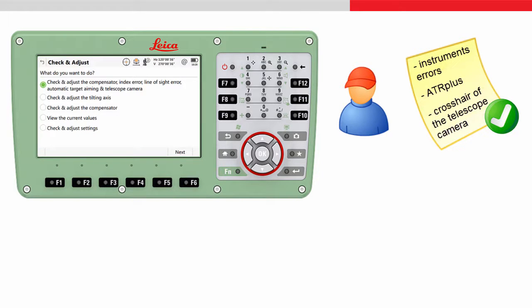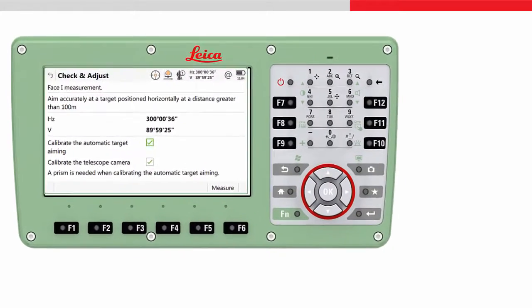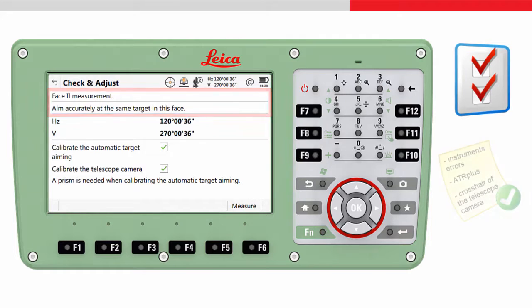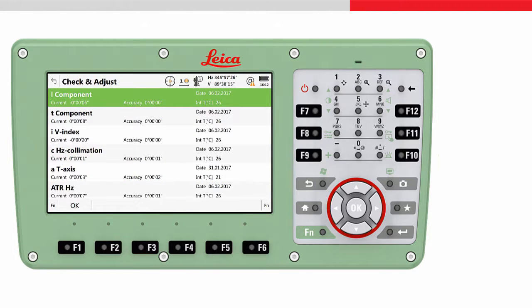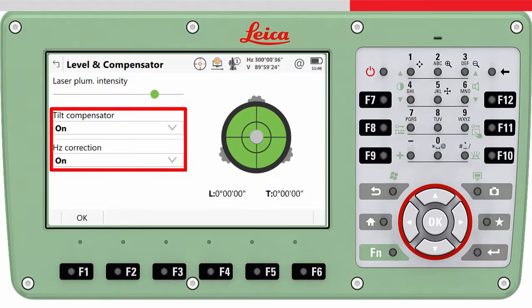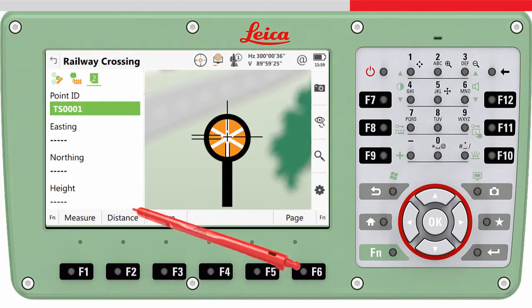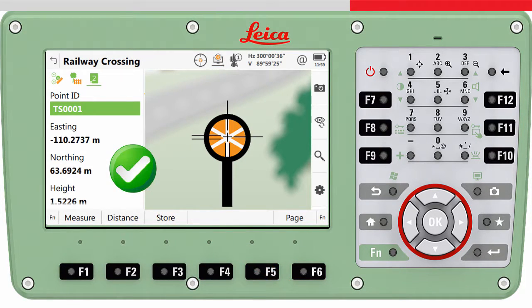It is not necessary to send the instrument to service to recalibrate it. The calibration procedures are guided and if they are followed carefully and precisely, the parameters will be correctly estimated. After using check and adjust, the calibration values will be remembered and automatically applied to all subsequent measurements when the tilt compensator and horizontal corrections are activated. This ensures your measurements are to the highest accuracy, meaning errors are minimised and you can have confidence in the results.